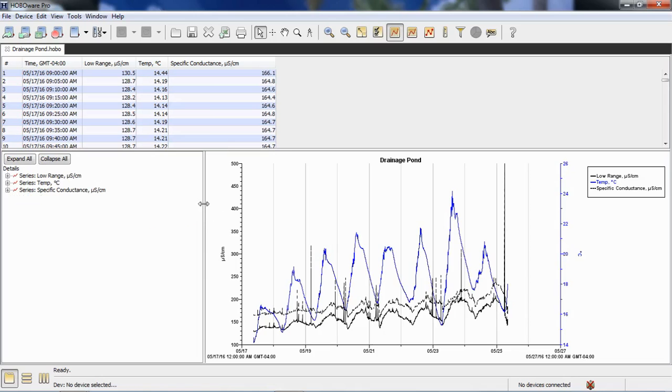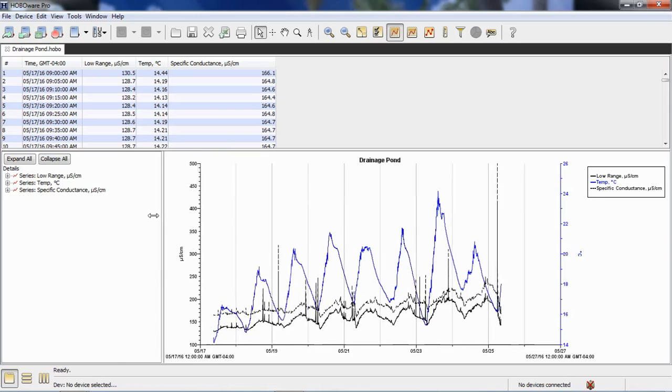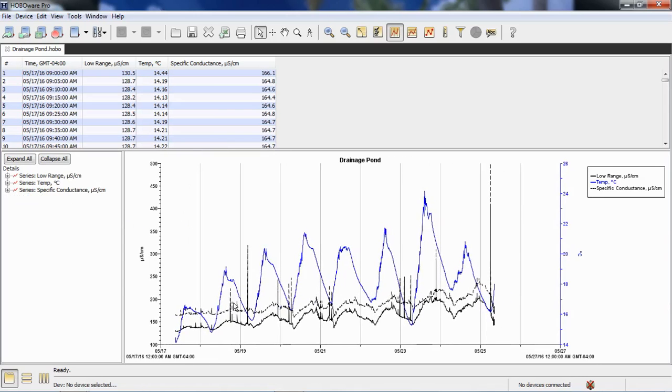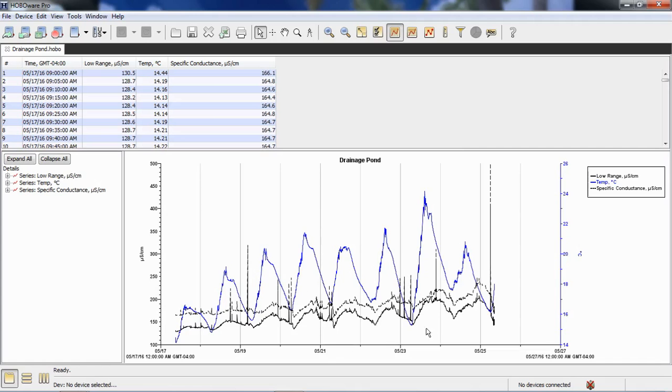You'll see there's some spikes in this conductivity data. I'm seeing some spikes up to a couple of hundred or even 300 microsiemens. And this could be related to something getting on the face of the sensor. Although it is a non-contact sensor, sometimes you'll see jumps in it from marine life or something else coming in contact with that sensor.